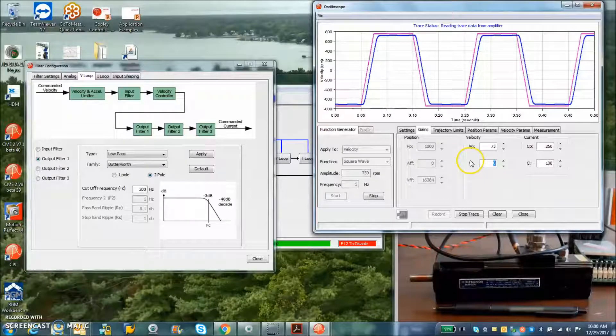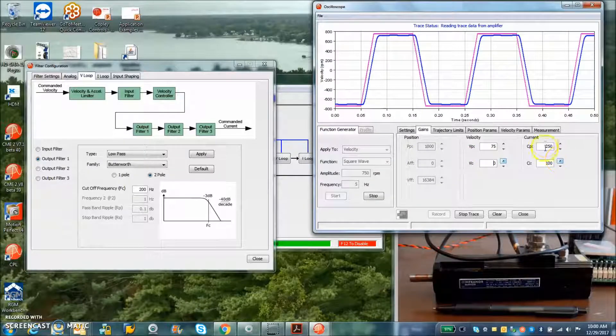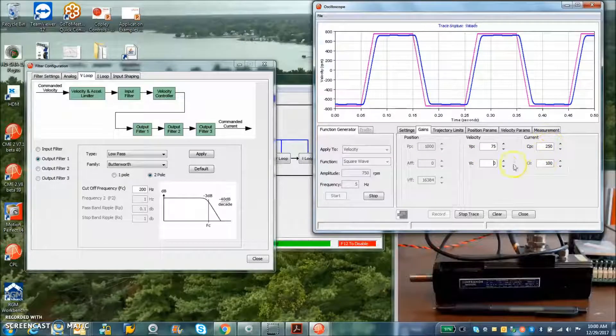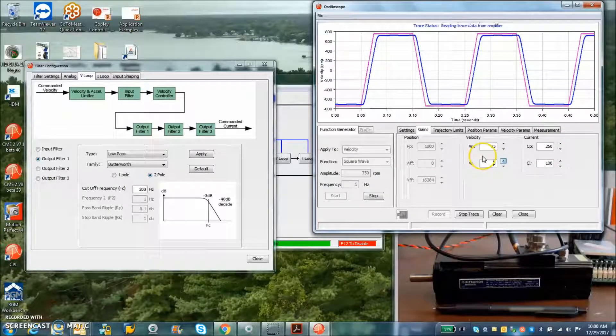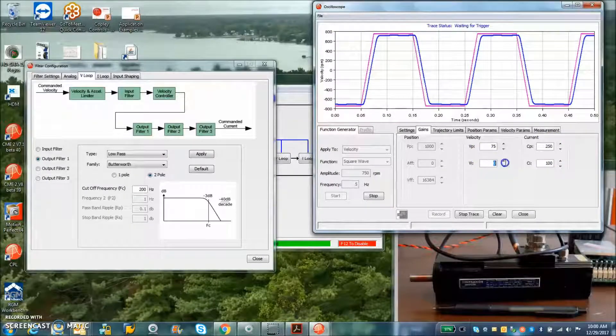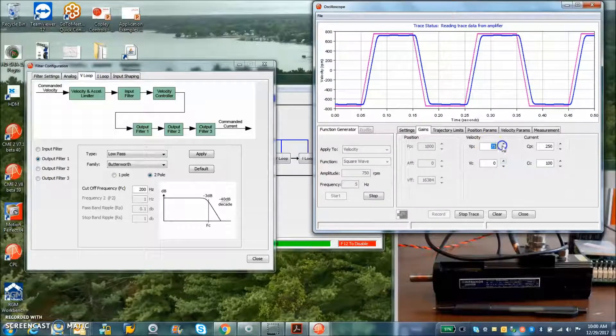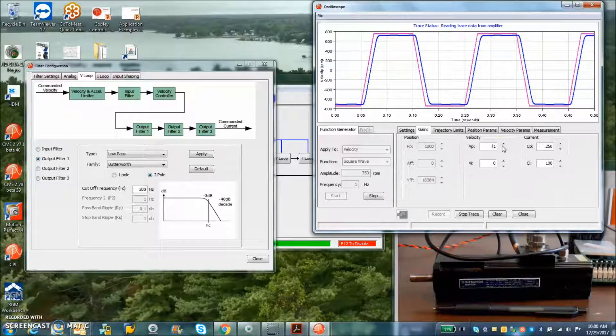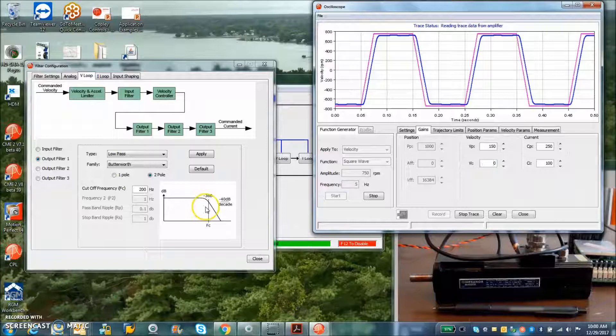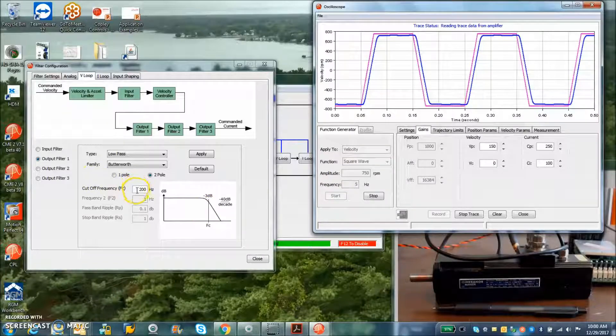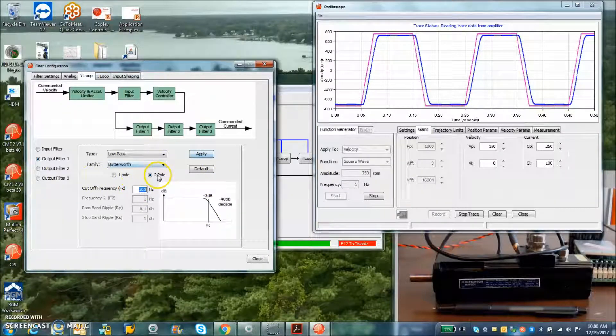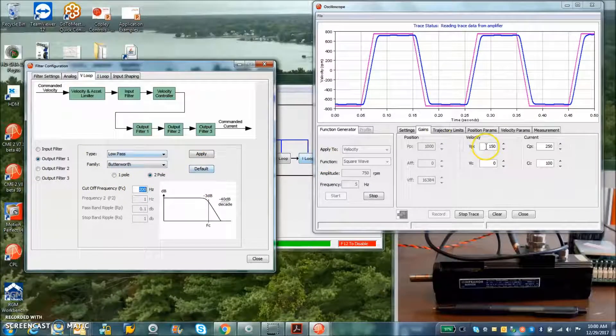I've got a little time, so I'm going to show the tuning of the velocity loop. Current loop is all done. Don't have to worry about it. 1.8 kilohertz of current loop bandwidth, so we can go fast. But I start with the integral to zero and start cranking up the VP. The default pole is 200 hertz here, two pole, low-pass filter.